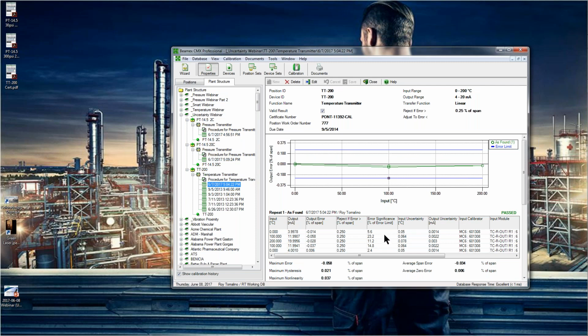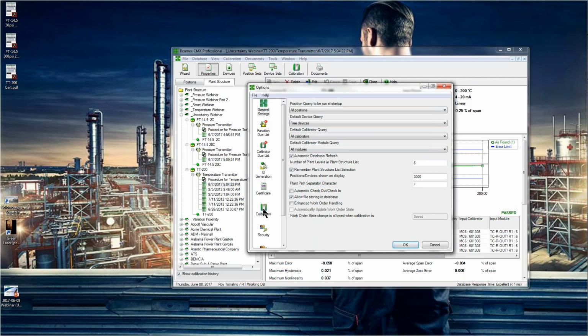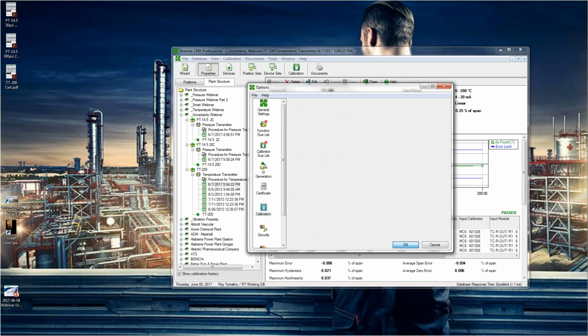Now, if I look at the table of the information, I've got an input uncertainty of 0.05 degrees Celsius, and an output uncertainty of 0.0014, so 1.4 microamps. Now, we have been talking about uncertainty, and uncertainty is sometimes difficult to grasp unless you can see it, and I want everybody to pay attention. I'm going to show it to you visually right now. I need to change one setting here. So let me go up and change it. I'll turn on show expanded uncertainty.